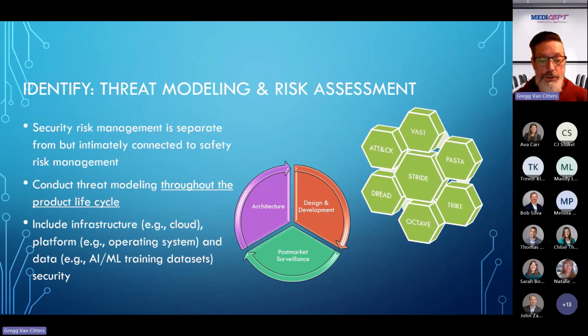Threat modeling is a continuous effort based on feedback from threat intelligence from organizations like Health ISAC, your problem resolution process from your software development framework, and various quality management system elements. So you're doing a lot of post-market surveillance, both internally, like audits in your QMS, and externally. Make sure you gather all that information and funnel it into your threat model.